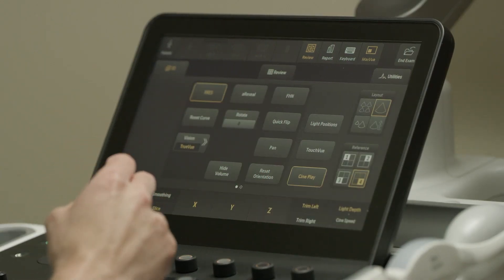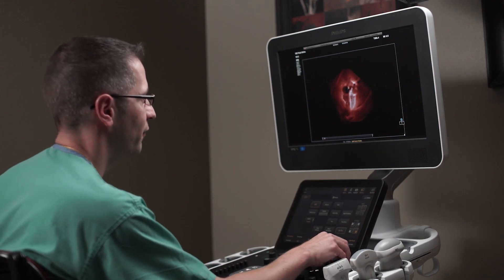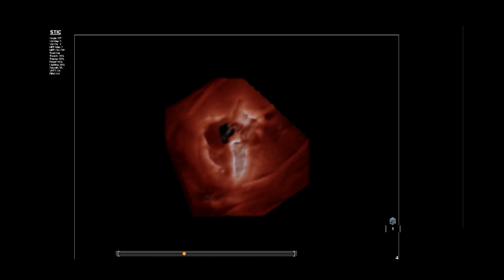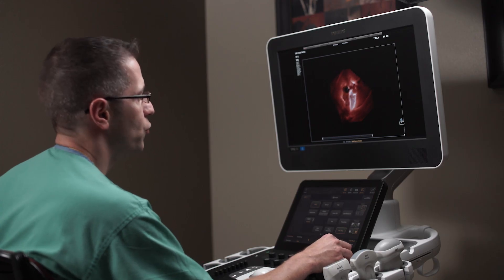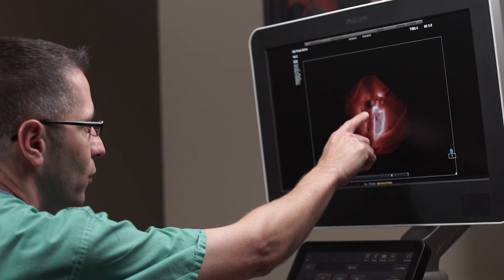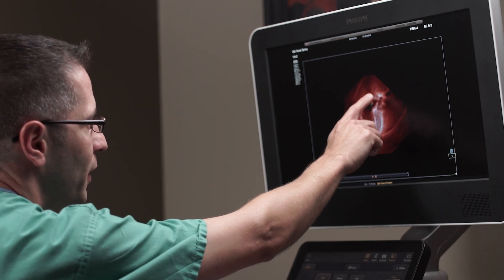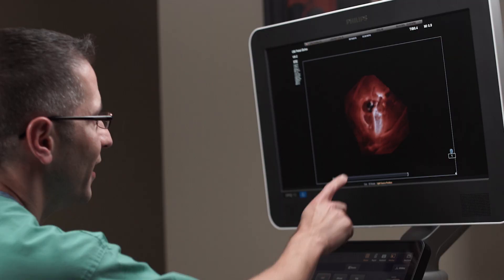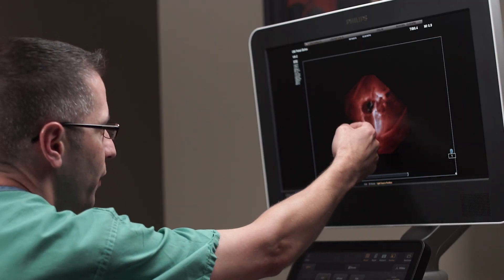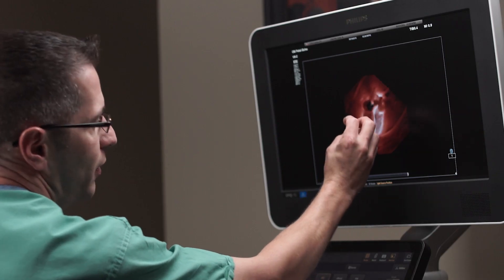When we move to TrueVue imaging, we have this pink hue that is simply coloring, but as you can see, I've brought the light actually within the left ventricle using the depth capacity, which is unique to TrueVue and allows the light to enter along a Z-axis. The light in the left ventricle allows us to see an illuminated left ventricle and the mitral valve. The light actually penetrates into the left atrium and illuminates the top portion of the wall of the left atrium, but does not enter the right ventricle — with no penetration through the ventricular septum — so the light is acting as it really would if I placed an orb of light within the actual cardiac volume.